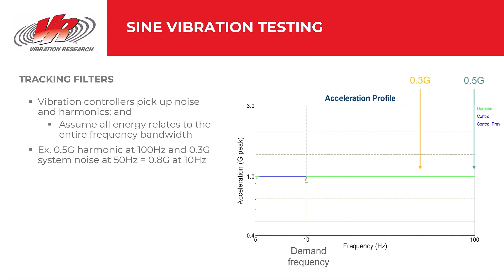When running a sine test, we're largely concerned with the control signal's amplitude at each frequency. The control signal helps us identify discrepancies between the drive signal, which the controller outputs, and the response on the shaker table. However, due to the inherent noise of shaker systems, vibration controllers pick up contributions from noise and harmonics in addition to this pure sine tone. Controllers assume all energy relates to the test's entire frequency bandwidth because controllers assume a perfect scenario.